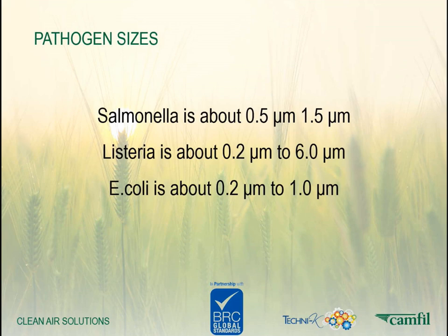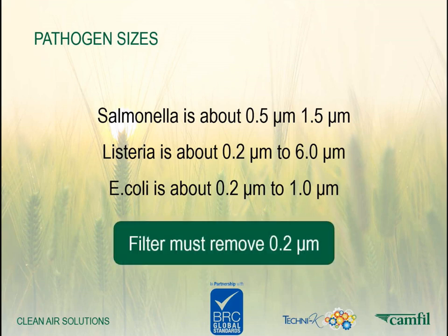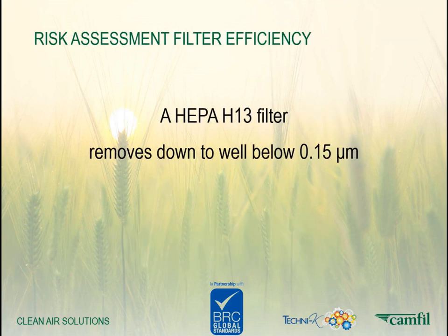So to do this, we need to know what the size of pathogenic bacteria are. So you can see here that they vary slightly, but the smallest would be 0.2 micron. So we need a filter that removes pathogenic bacteria that are 0.2 micron. Well, that's a $1 million question, as what filter size does that? Well, I'm going to cut to the chase and go straight to the answer. So we need a HEPA H13 filter, as this will remove down to or below 0.15 micron.